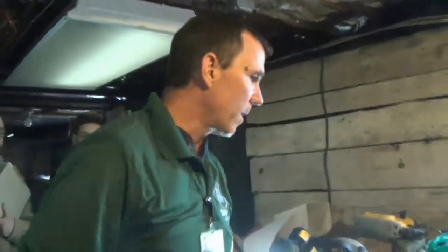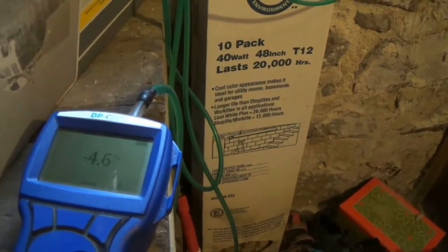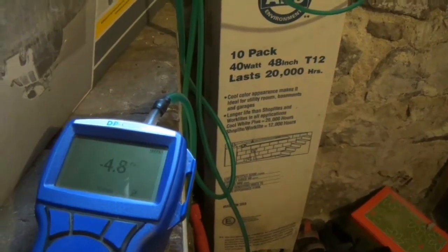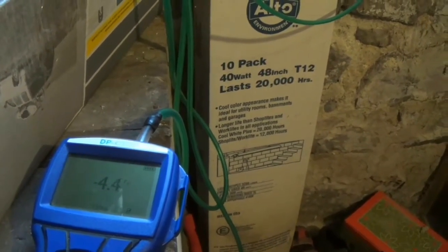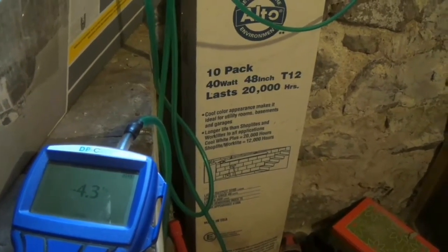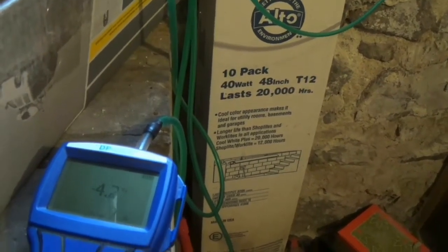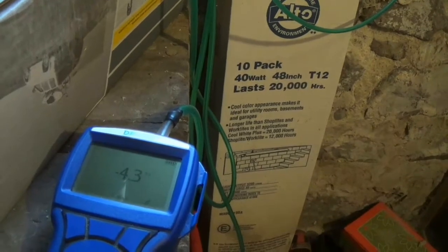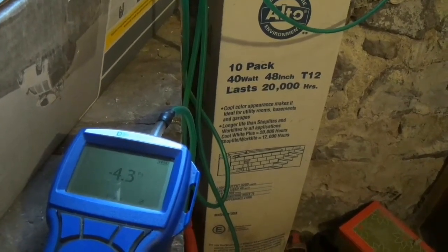And so what we want to look at now is what's our number after we did all that, and it is a more negative number than what we had before. So we have a minus 4.6. And so going from minus 3.8 to minus 4.6, our total depressurization, or our total change in pressure, sometimes it's pressurization, you can increase pressure in the summer sometimes, usually not. Total change in pressure is minus 0.8. So I write that down.